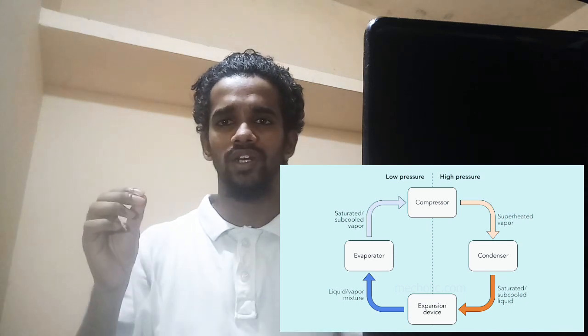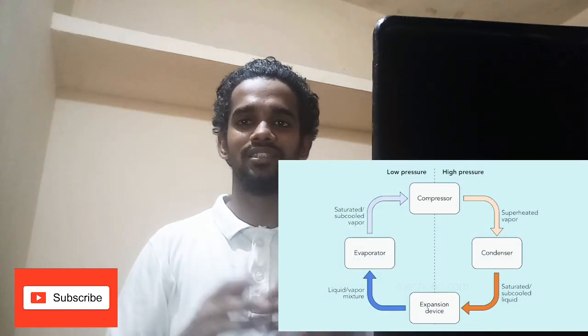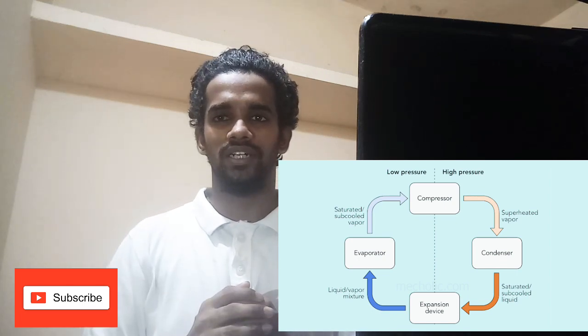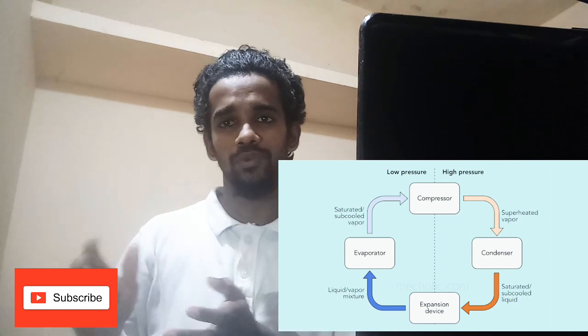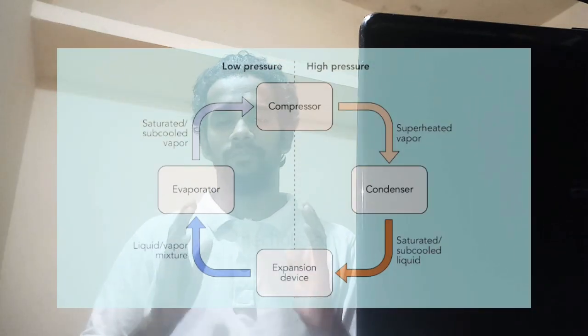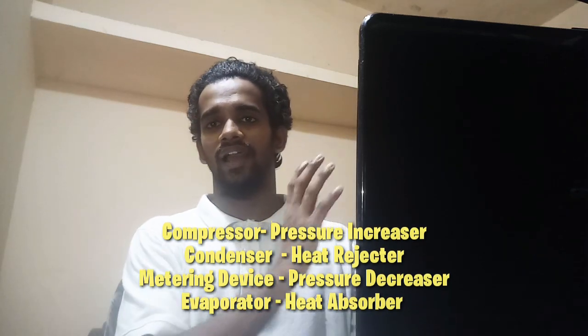Now talking about the evaporator: refrigerant entering the evaporator section will have a low saturation temperature, so the boiling point of that refrigerant will also be low. It receives the latent heat from that particular room or cabin and boils off. The liquid refrigerant boils to a superheated vaporized form and is sucked into the compressor, where the pressure of the refrigerant is increased, and so is the saturation temperature. From the compressor, the vaporized refrigerant with high saturation temperature and high pressure comes to the condenser, where it condenses to a liquid form and is subcooled to a temperature below that of the seawater or air. This is how the refrigerant cycle works: compressor, condenser, metering device or expansion valve, and evaporator — that is, pressure increaser, heat rejecter, pressure dropper, and heat absorber.